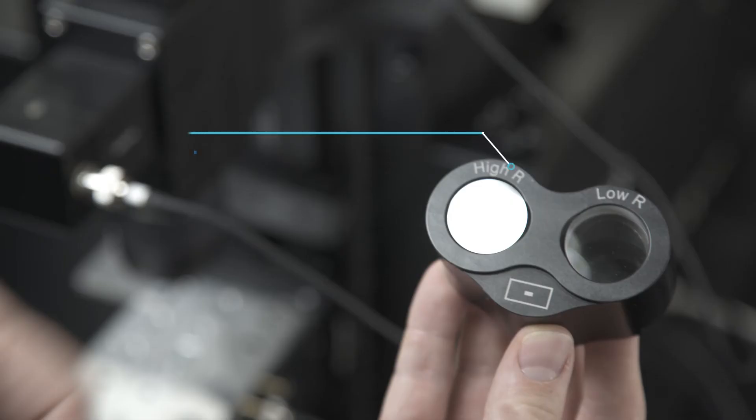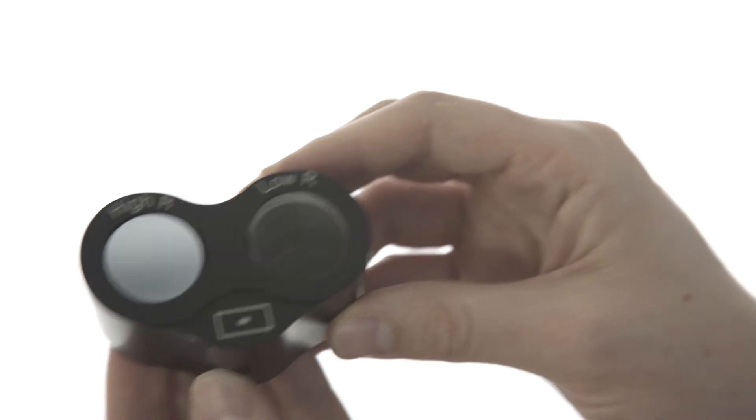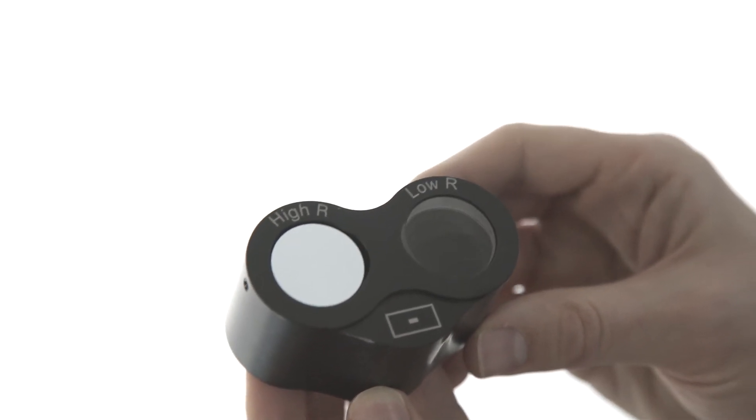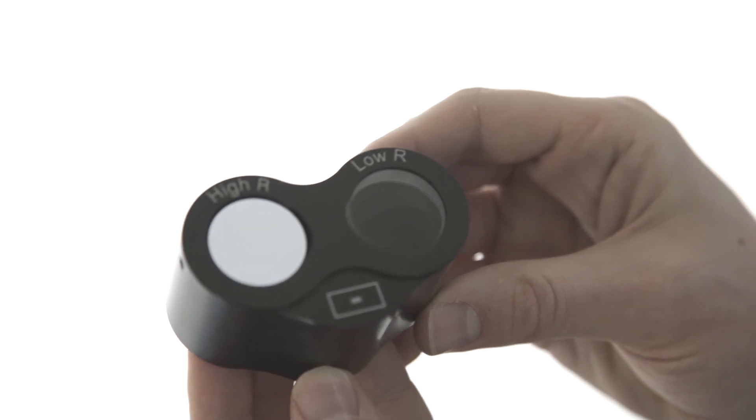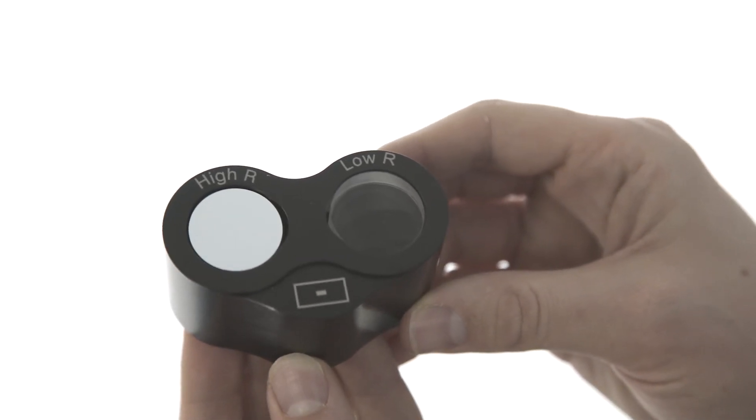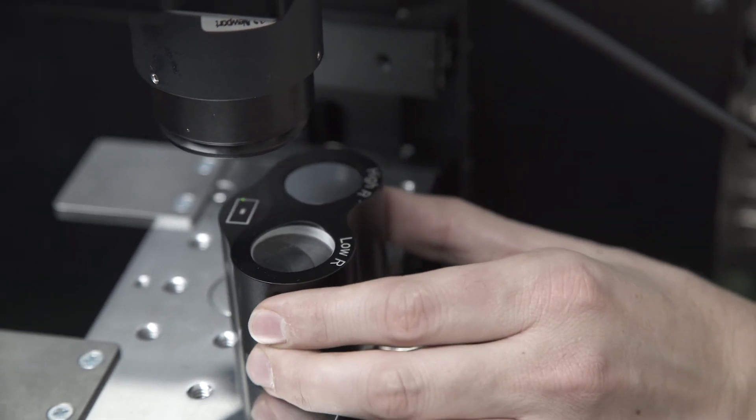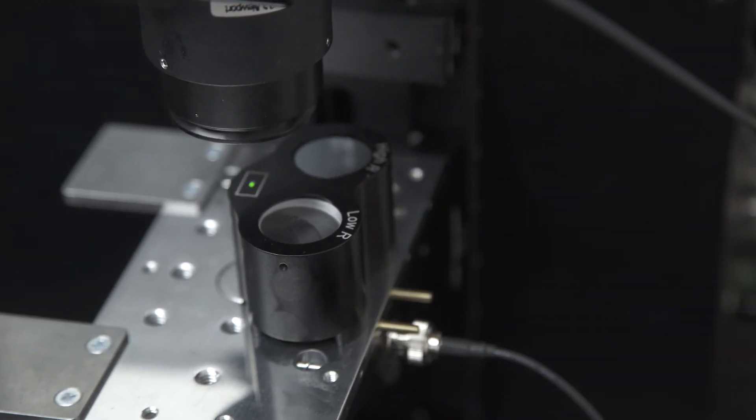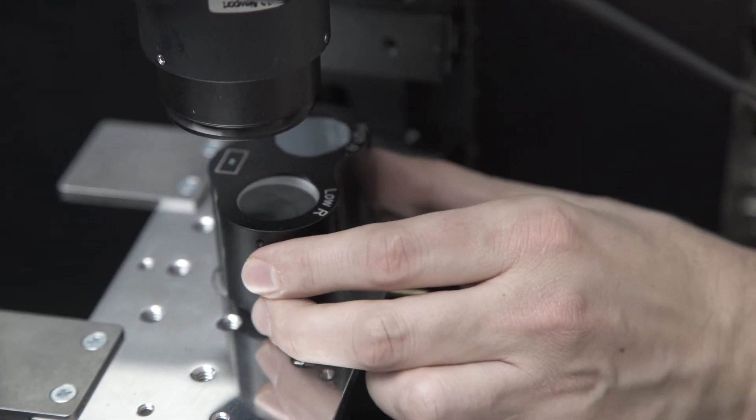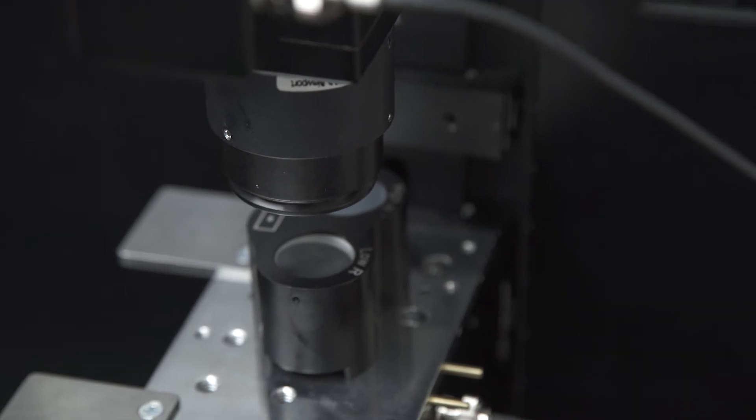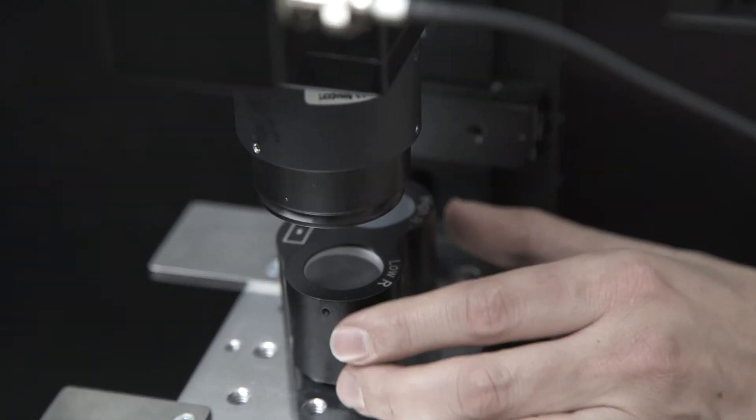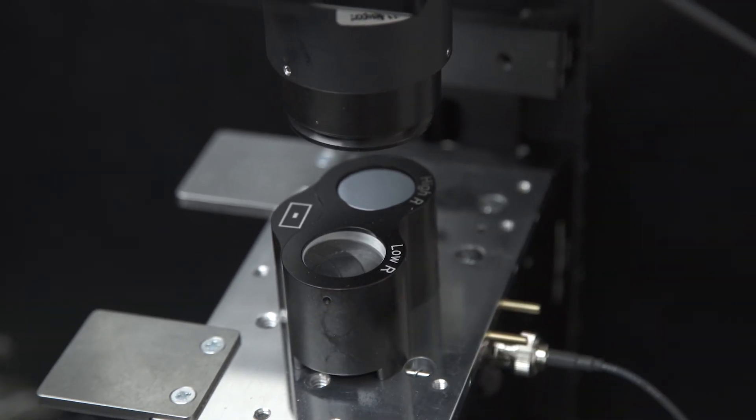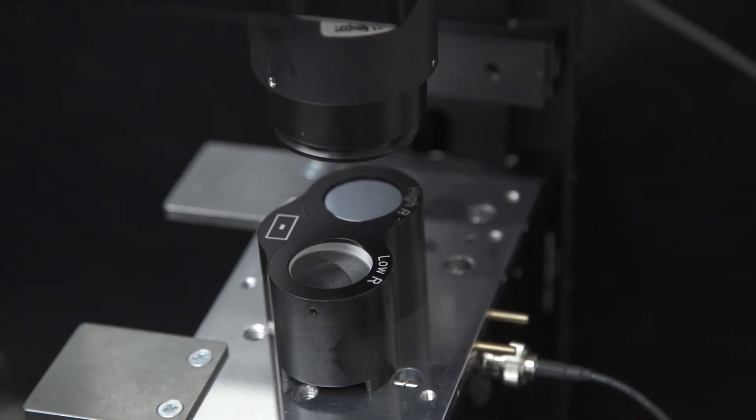This is the reference standard containing both a high and low reflectance optical component, which is used to calibrate the reflectance detector and ensure accurate internal quantum efficiency measurements. There are no electrical connections necessary. To verify the working distance, place the standard on the stage with the focusing target, the small rectangle, in the light path. The output beam size should resemble the size of the target. The high and low reflectance optics are at the same height as this target. Simply align the standard underneath the output beam.